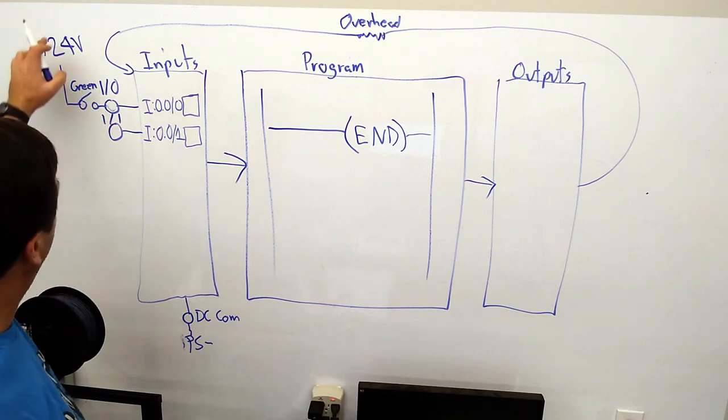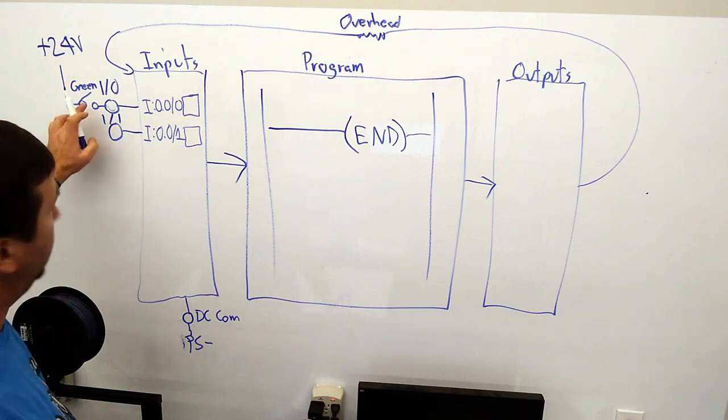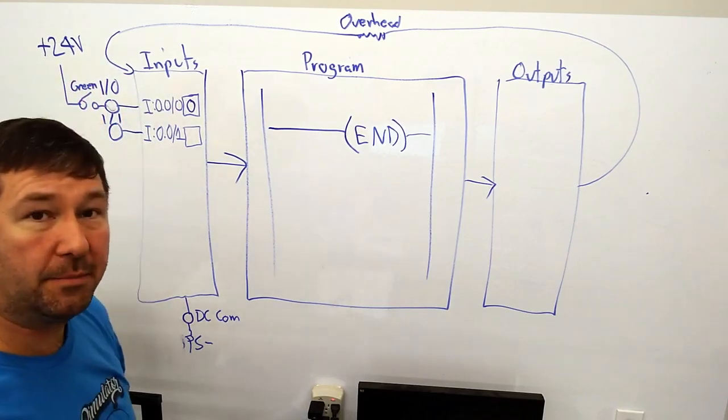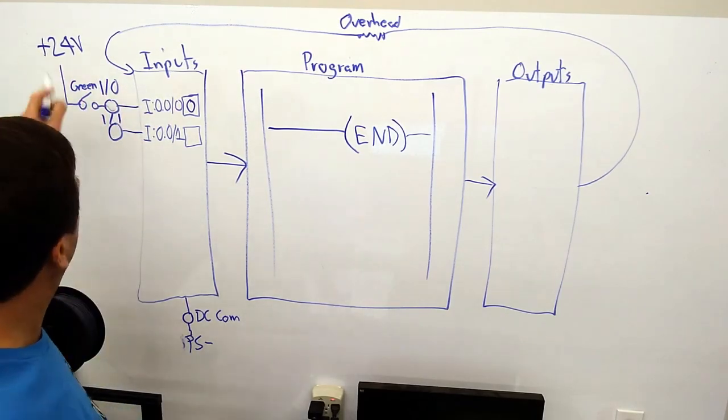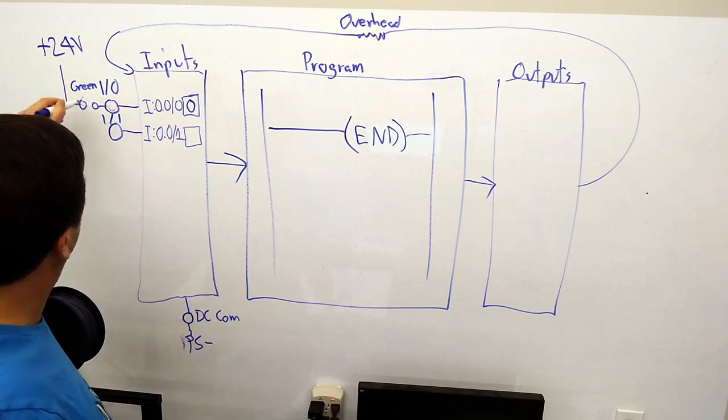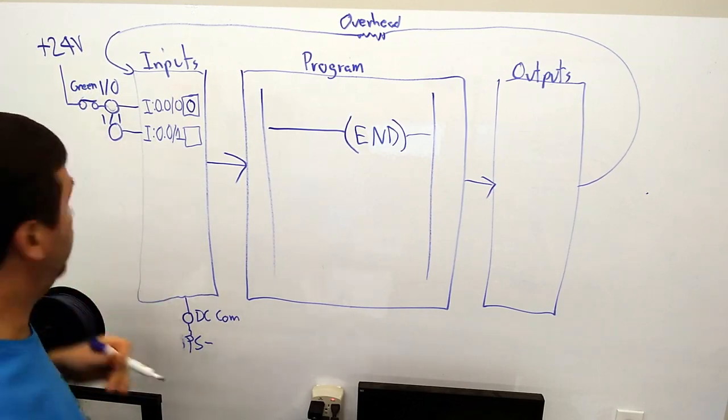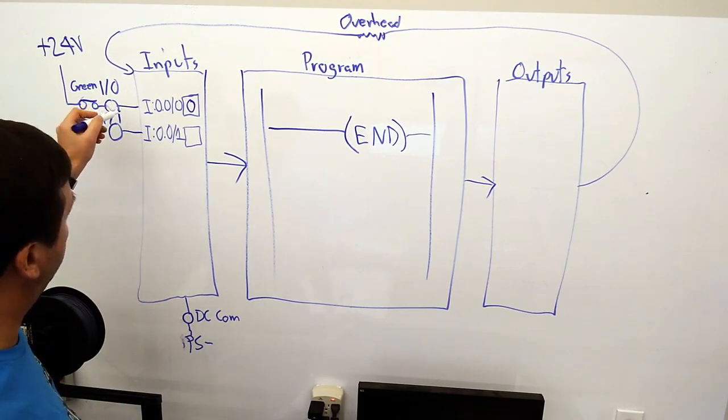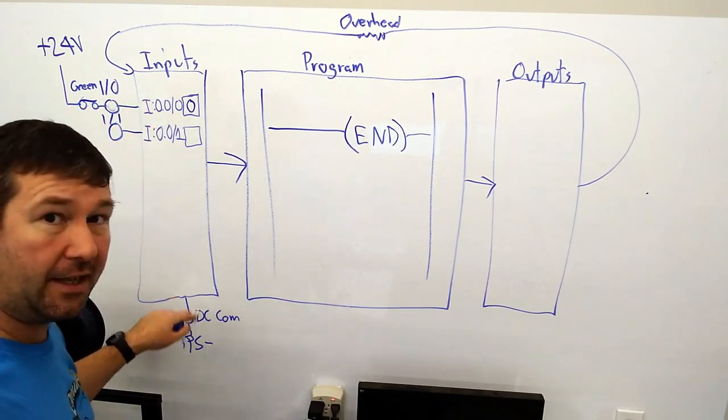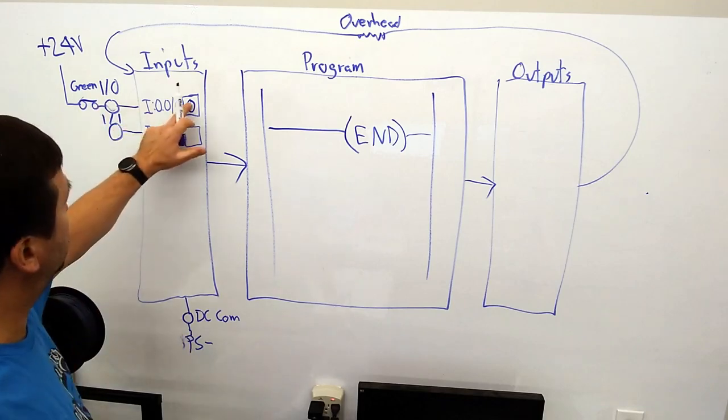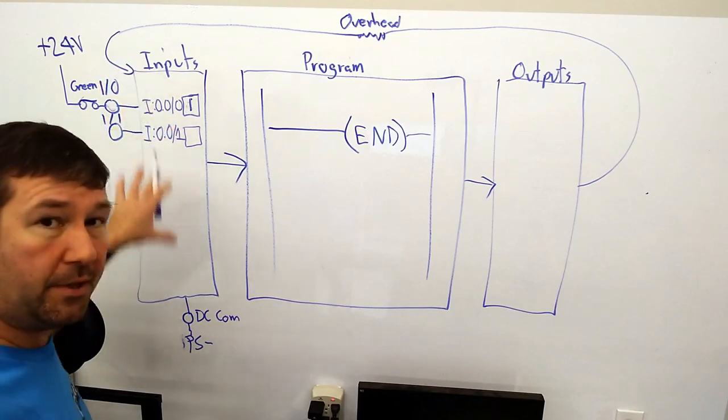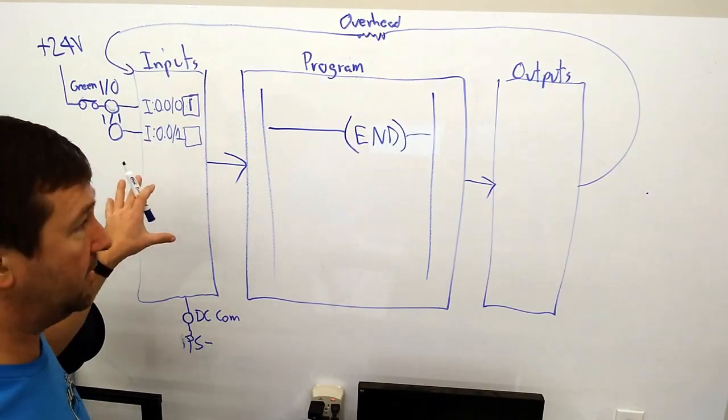So right now, we ask ourselves, do I have current? I have 24-volt, it's coming to here, but my switch is open, so it says no, and it puts a zero there. Now, if I close this switch and I ask myself, do I have current, I have 24-volt, my switch is closed, I have a continuous path to my terminal, module is good, I get to DC-COM, so yes, I do have current, and that will be a one. And it does this for every input each time it goes through its input scan cycle.